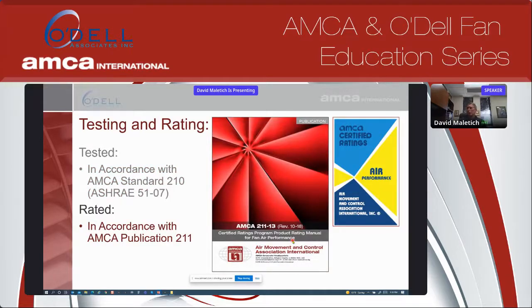Fans are rated in accordance with AMCA Standard 211, and that's how we catalog the performances. Basically, what that means is that we take the curve that was tested in accordance with AMCA Standard 210, and we rate it roughly plus or minus 2.5 to 3% on flow and pressure, and 5% on energy consumption, and that's what is allowed to be put in our catalogs.